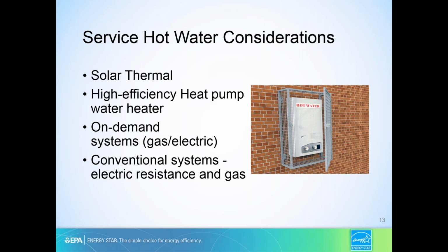We've also included heat pump water heaters at all the fire stations. This was a great implementation model because we took an existing building with high demand—these guys live there, washing dishes, taking showers, so there's a lot of demand for hot water. Instead of using electric resistance and not having the option of gas, we went with a hybrid heat pump water heater.